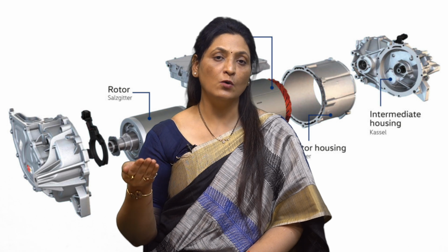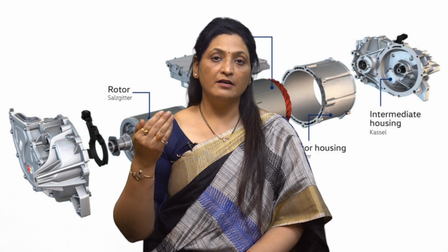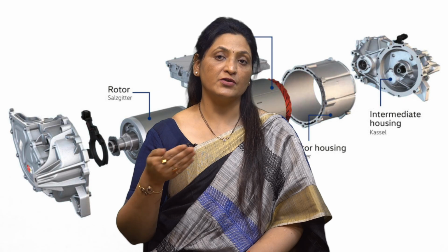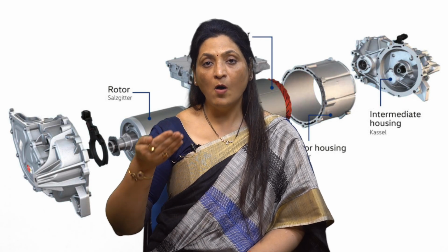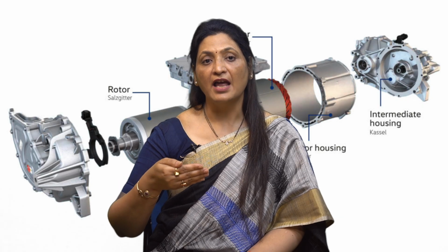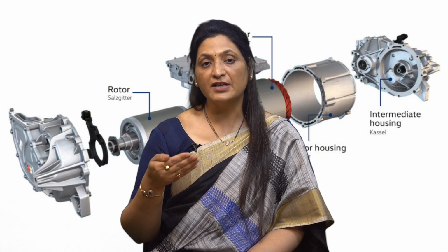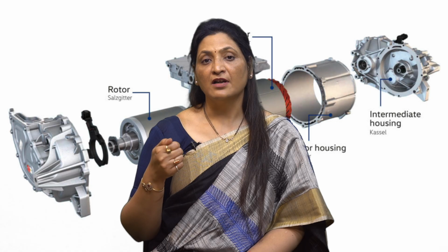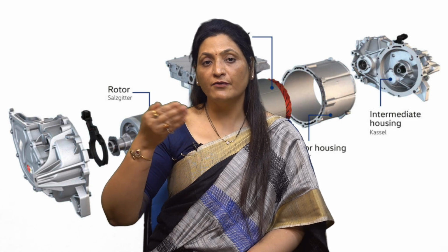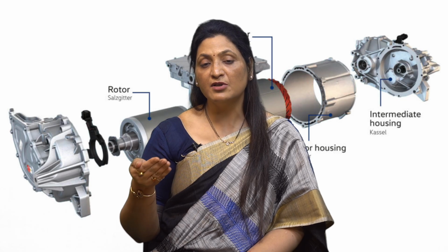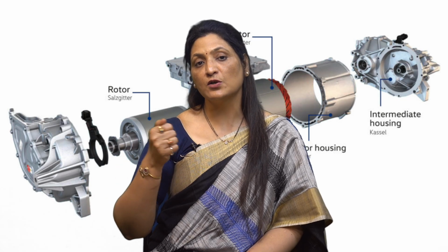Let us have a look at them. The range over which the speed control is necessary for the load, similarly how hard it is to control the speed, and the speed regulation affect the choice of the motor. The motor efficiency varies as load varies. So, efficiency consideration under variable speed operation affects the choice of the motor.